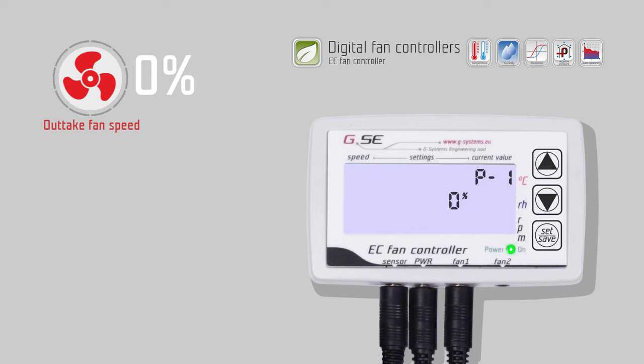Now you can set the speed, which should correspond to 1% of the minimum speed. Press Set Save. Use the up-down arrow keys to change the value. And press Set Save to save. Repeat this process, and keep increasing the value until the fan is able to turn by itself. Press down to go to end, and press Set Save to confirm. The EC fan controller initializes with the new settings.